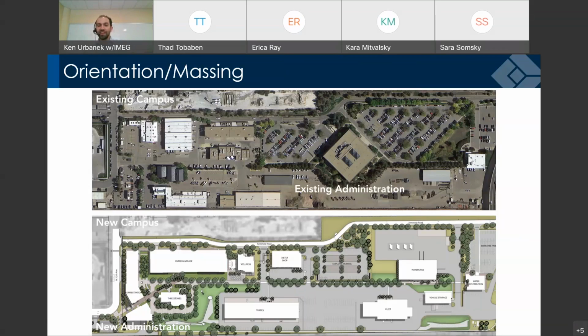We're limiting our exposure on the east face, although we have this large exposure on the south, we can actually control the solar gain a little bit better until then we get to the west face and we're, again, minimizing that. And sometimes it's a little bit not intuitive to think the facing glass to the south would actually be better. But again, it has to do with our ability to passively control that solar load, which is primarily one of the bigger items you run into in a highly glassed building like this administrative building.